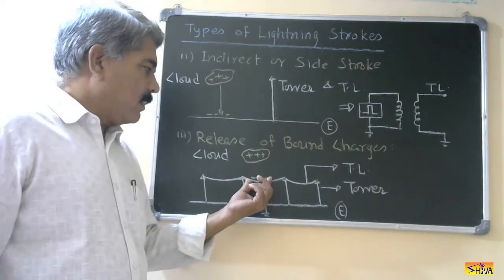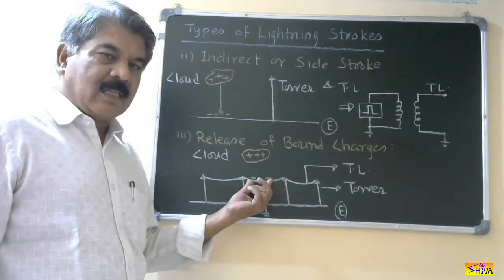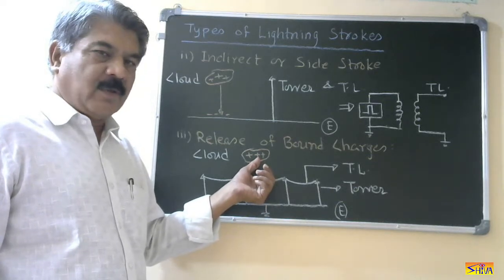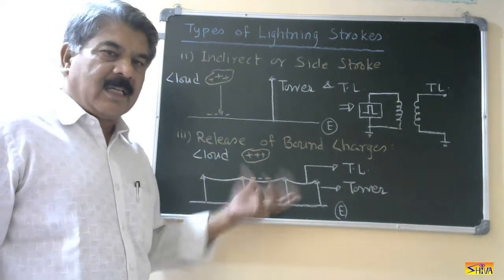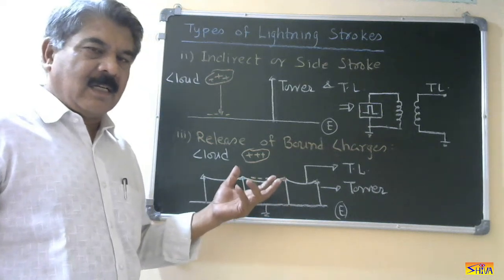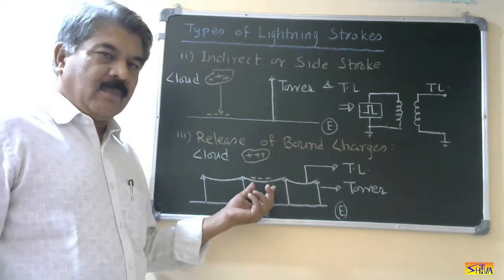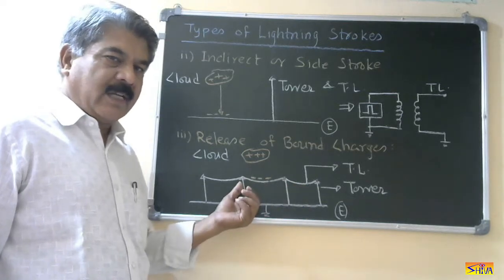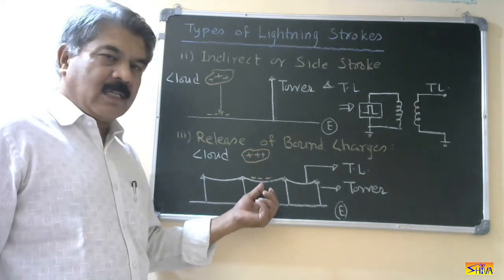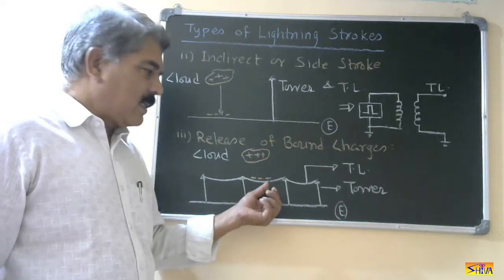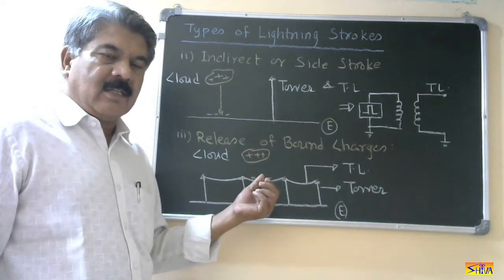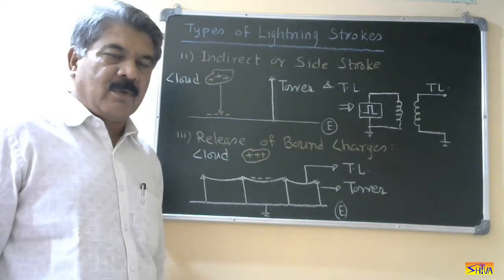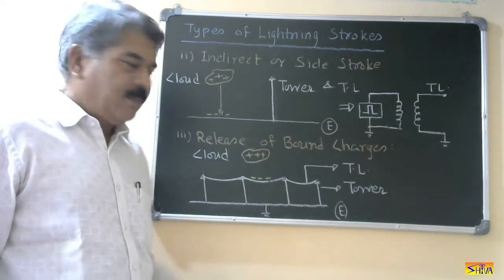In that case, the negative charges which were held up on the transmission line due to the presence of the positively charged cloud will be suddenly released. When these charges are released, they establish traveling waves of high magnitude in both directions. If the total charge is Q, then charges will flow in both directions with magnitude Q/2, establishing traveling waves in the transmission line.